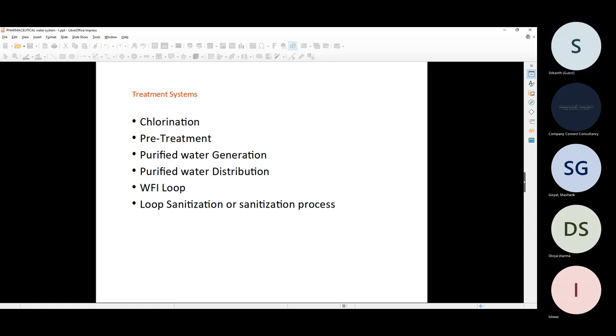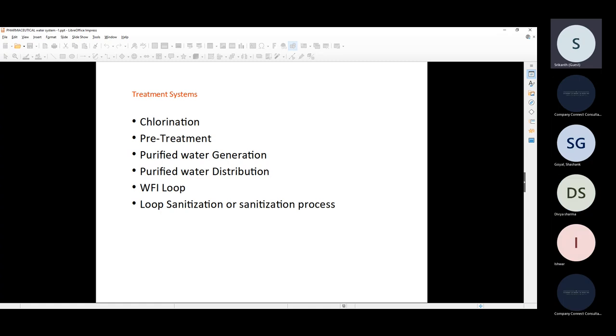Next, coming to the pre-treatment, we will have the MGF, UF, and a softener, and RO systems also. In detail, I will explain what the MGF will do, what the UF will do, why we require that, and what the other processes are. As of now, I'm just telling you broadly. We call this the pre-treatment. In that, we can have flotation, adding alum for TSS, total suspended solids. TSS will be removed in the MGF, and if they are in a higher concentration, we have to use other methods like adding alum and floating.